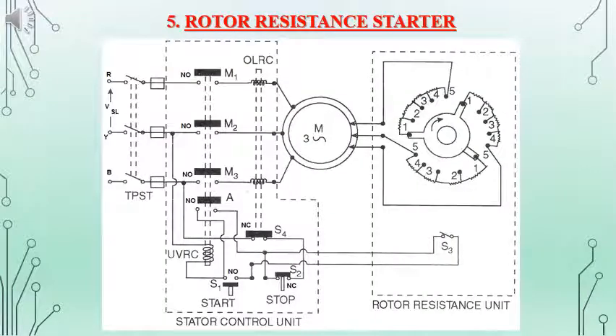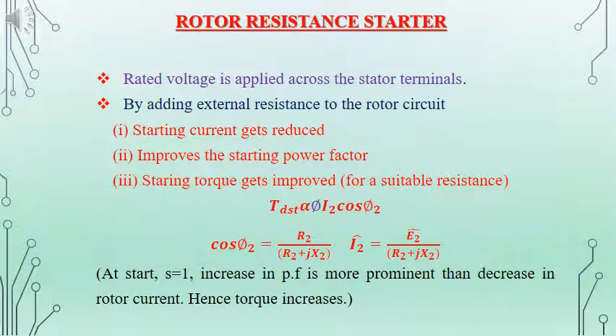Here we have the circuit for the rotor resistance starter. The stator control unit is the same as that of the DOL starter, but on the rotor side we have a variable resistance unit. After starting with the stator circuit, we can control the rotor resistance to adjust the current and the torque of the machine. The advantage of the rotor resistance starter is that for starting we can apply the rated voltage itself across the stator terminals, and by adding an external resistance to the rotor circuit, we are able to reduce the starting current and improve the starting power factor and the starting torque.